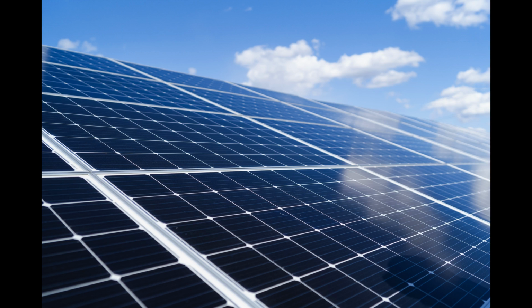The other thing is solar panels now, they typically produce about 50 volts of electricity, which in itself isn't a whole lot. I mean, it won't kill you, but it could burn you a little bit. But when you put the system together, all the solar panels together can produce as much as 1,000 volts, and you can weld with that. Not only can it burn you severely, it can kill you. When it is transformed into alternating current, it has to be installed in such a way that you don't have loose wires, shorts, and so forth. These are the kind of precautions that a qualified electrician would make. You have to have some knowledge of electrical installations.